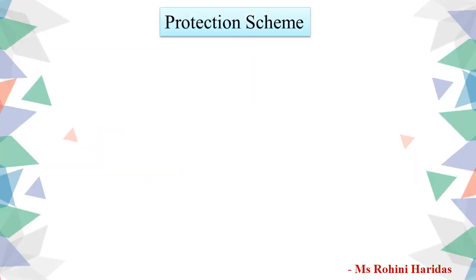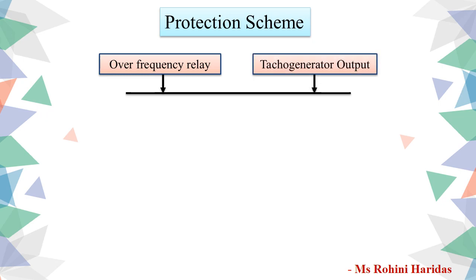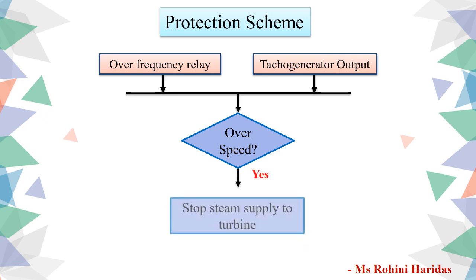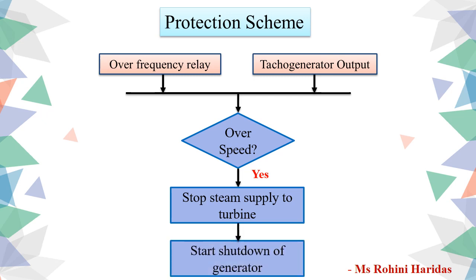Now let us see the protection scheme. As discussed previously, overspeeding can be detected either by using the overfrequency relay or by monitoring the output of the tachogenerator. We will take the input from the tachogenerator and determine whether there is an overspeed or not. If there is an overspeed, then stop steam supply to the turbine and start shutdown of the generator. This is the logic behind the protection against overspeed.